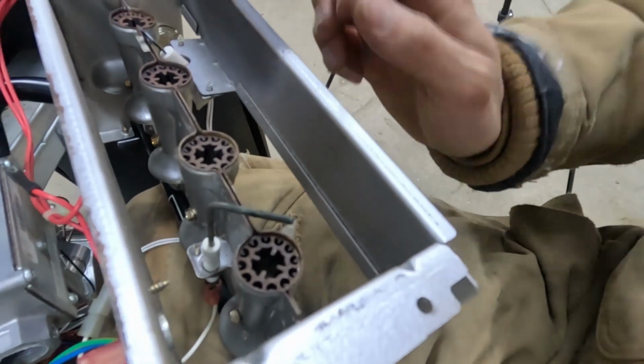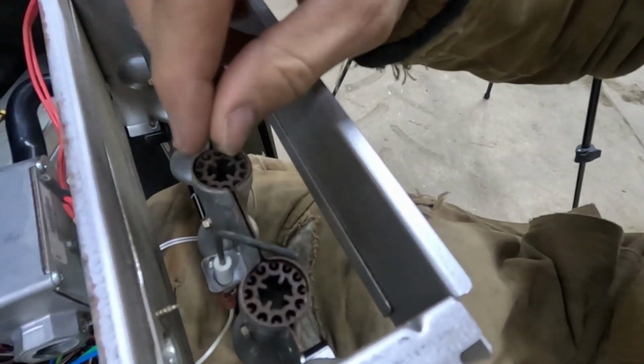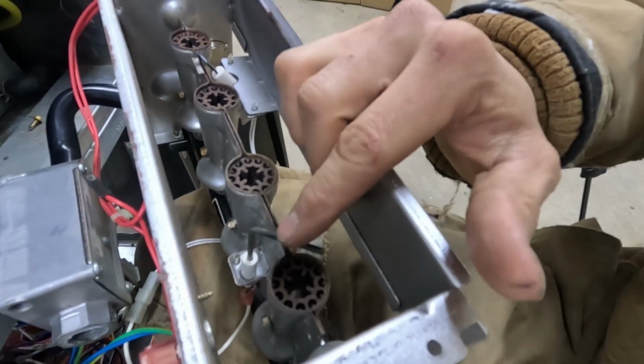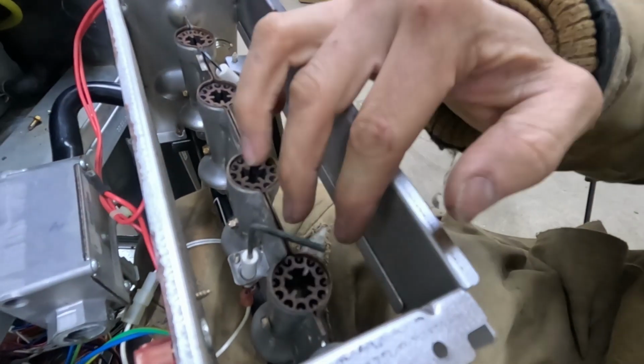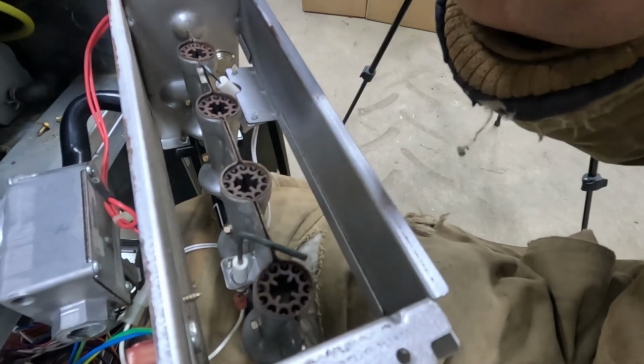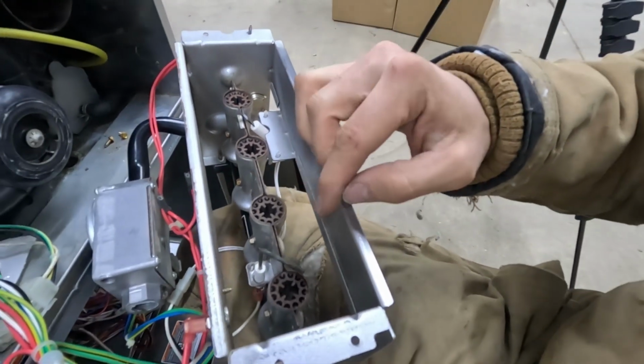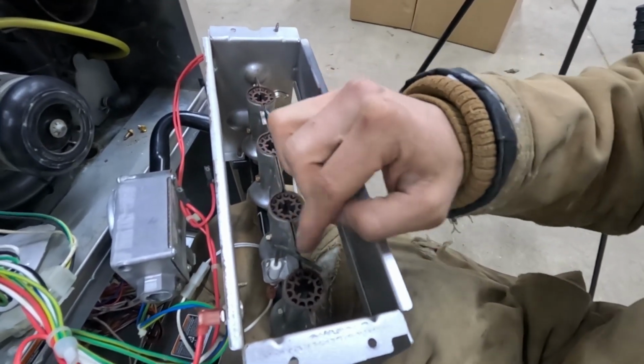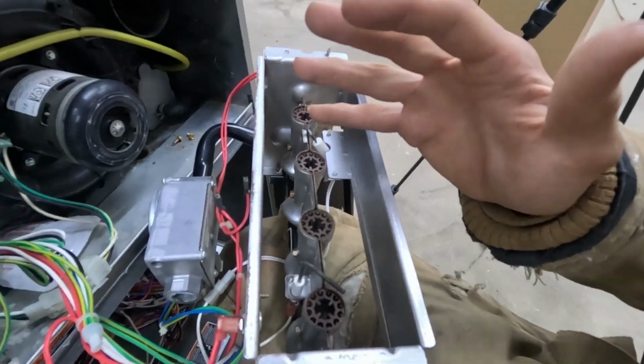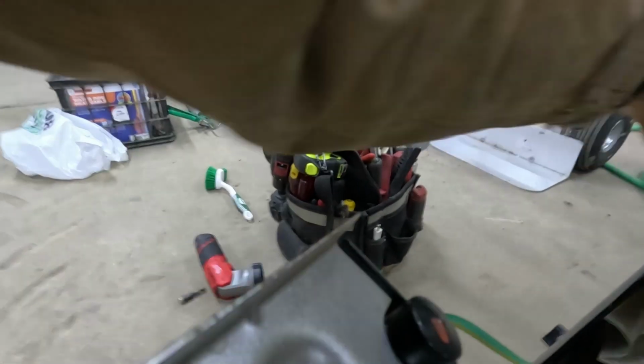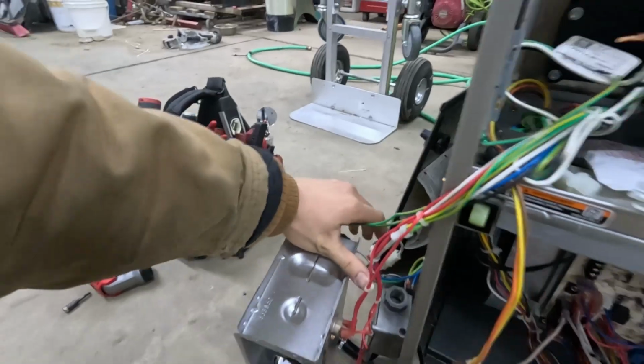You can just use a piece of emery paper and brush that up, get it all shiny, because that's actually a conductive connection. As the flame crosses it, flames are conductive, and it'll send a voltage out on this probe, and the board will read that as a microamp draw. And set this down here, out of the way.